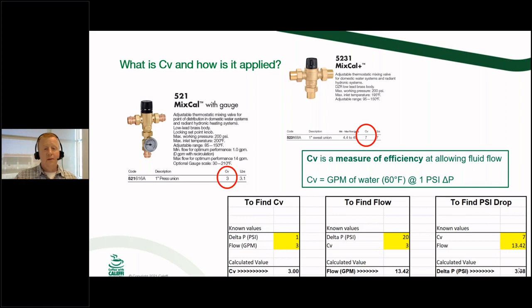So definitely consider this. Again, I think the biggest thing to stress here is to not size your valves based on pipe size, but to figure out exactly what your flow requirements are. And I know that can be a real trick on some of these jobs, especially older jobs that have been remodeled a zillion times. But there are water demand calculators out there from IAPMO. You can talk to an engineer. An engineer especially can go through and count the fixture units and figure out what you actually need. It gives you a little bit of protection from liability because you've got somebody designing that system.